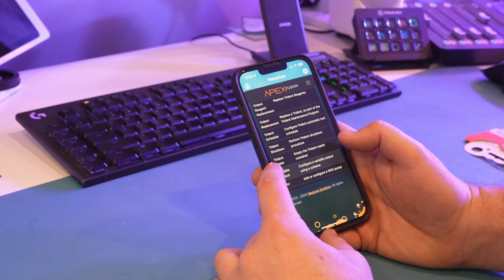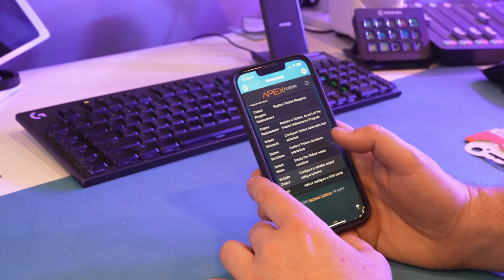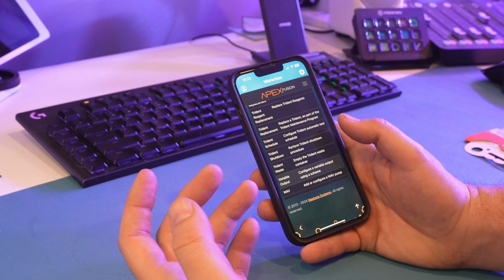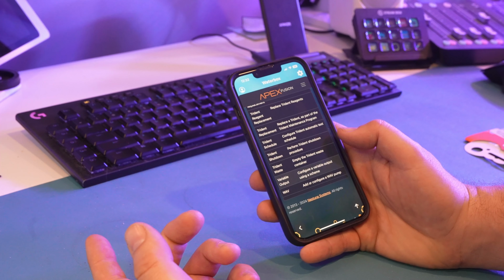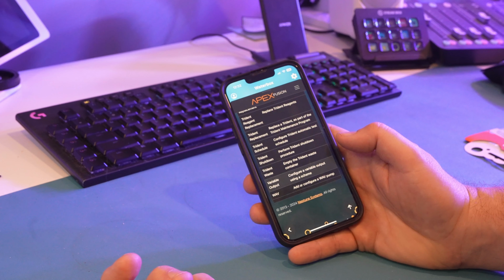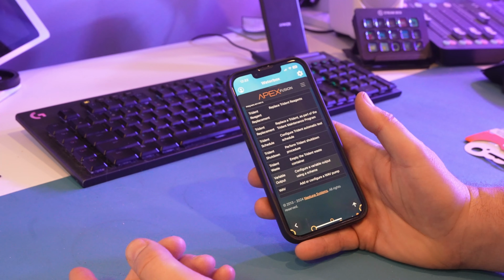Now before you actually disconnect your Trident, you want to make sure you run the Trident shutdown procedure. And this involves removing the sample line from the tank and all of your reagent containers. Let's just make sure all the lines are emptied out before you get to it. So run that. After that, you're safe to disconnect it.